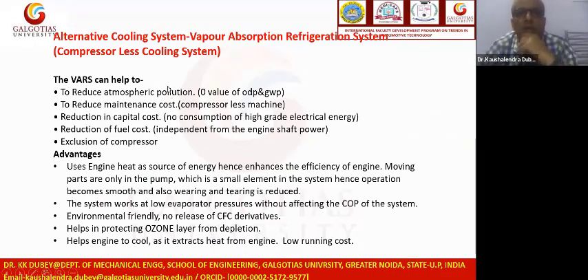Now the available alternative cooling system is the vapor absorption refrigeration system. The existing system is the vapor compression; here the vapor absorption system is available. For the vapor absorption, there is no requirement of a mechanical compressor. There is no requirement of any high ODP and GWP refrigerant. It requires only and only the heat source. There is no chemical based refrigerant required. It requires ammonia and water, or the lithium bromide type system, which have zero value of ODP and GWP. So there is no atmospheric pollution and no severe atmospheric impact.